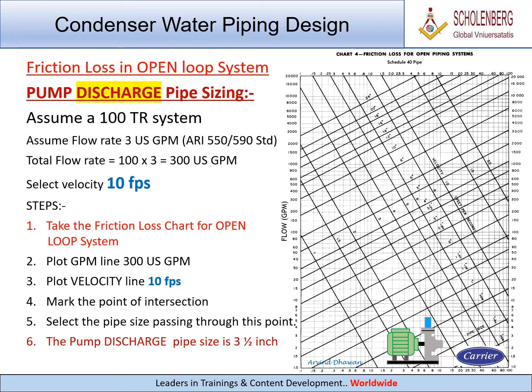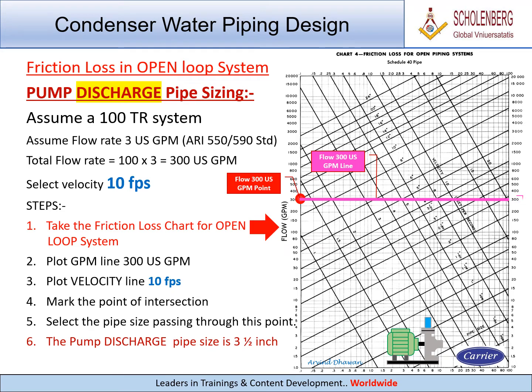Steps: 1. Take the friction loss chart for open loop system. 2. Plot GPM line at 300 USGPM. 3. Plot velocity line at 10 FPS. 4. Mark the point of intersection.